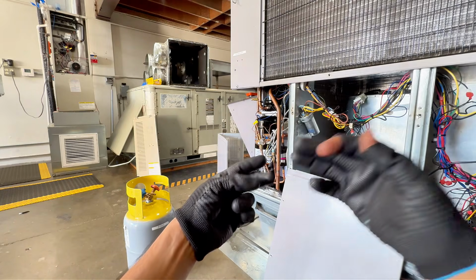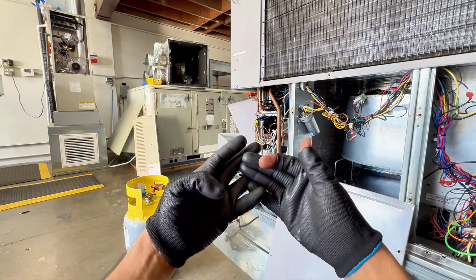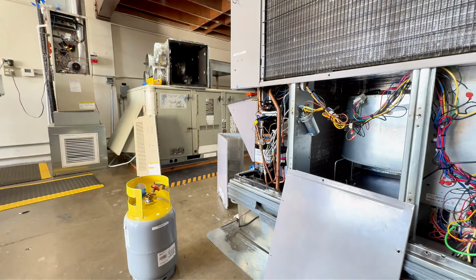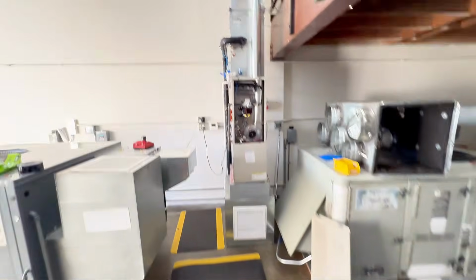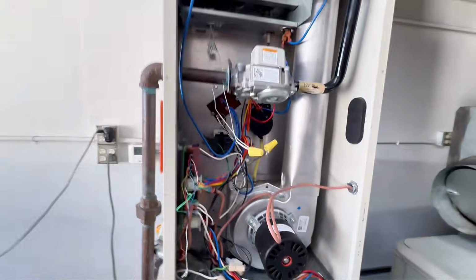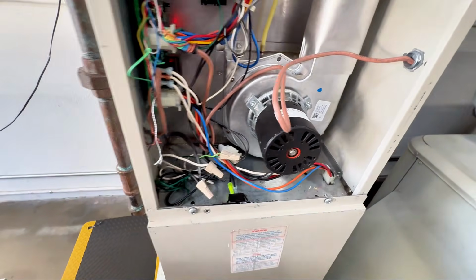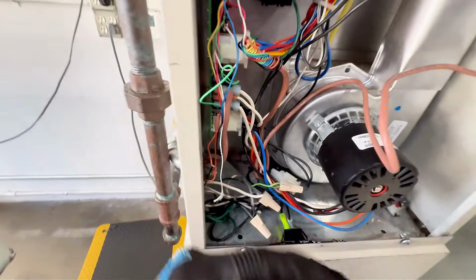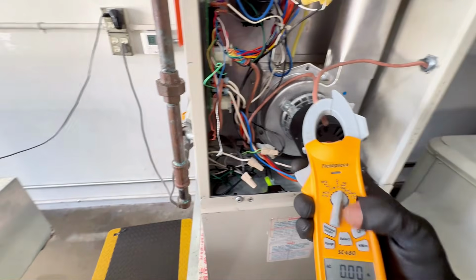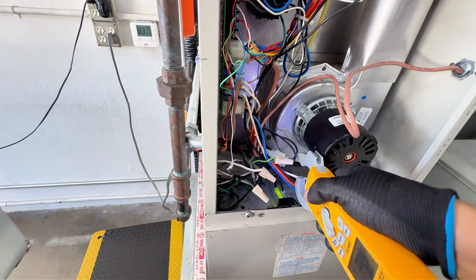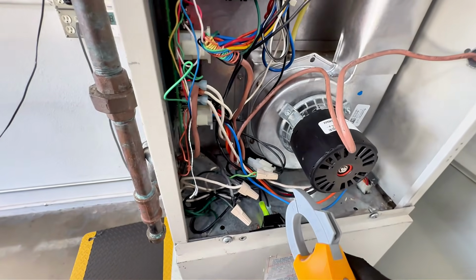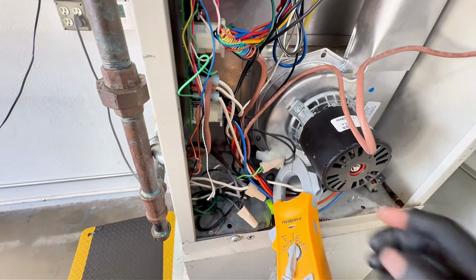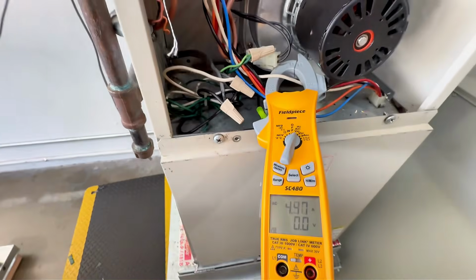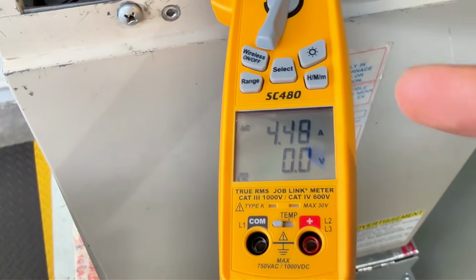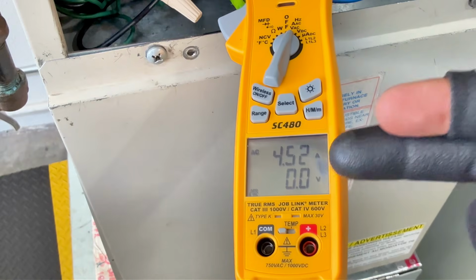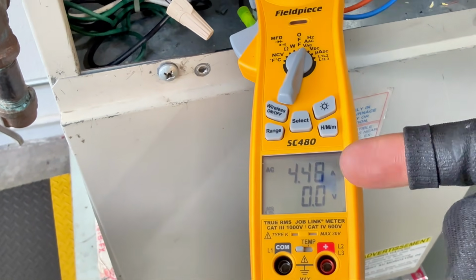Whether on the supply side, closed supply vents or dirty filter, which is going to pull more? Which is going to pull less? Well, let's find out. Let's go ahead and do the PSC first. So right now I have it on the fast speed. It's cooling right now. So I'm going to go ahead and check my amp draw. I'm going to put it on amps, and I'm going to check the neutral here. Give me 1 second here. Okay. So right now, we are reading 4.5 amps. That's how much we're pulling right now.